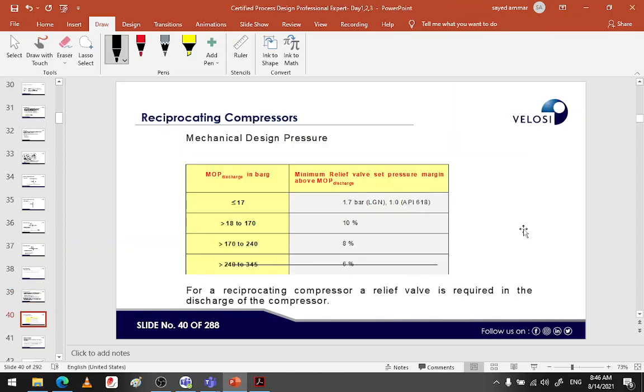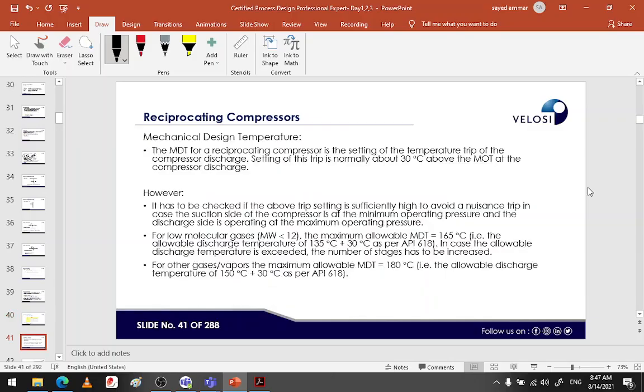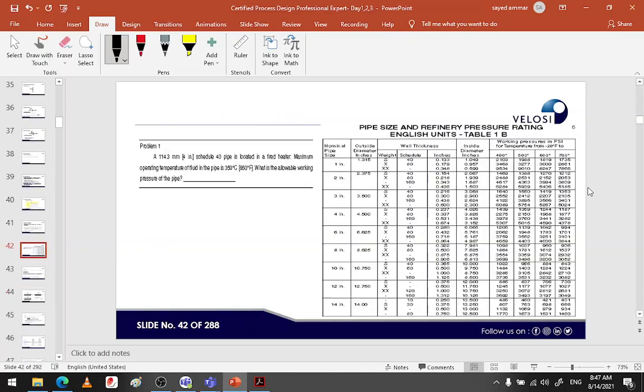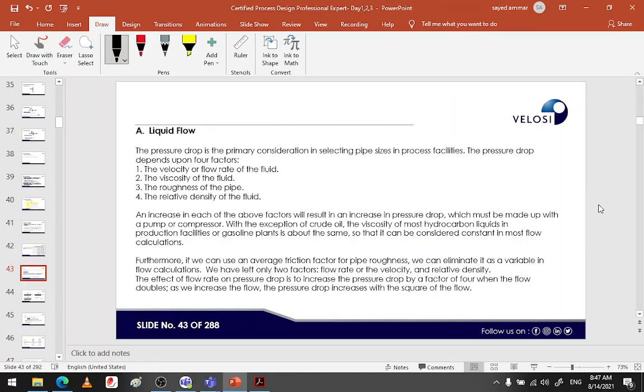This is the same table from another company. Flow less than 17 will add 1.7, between 18 to 170 will go 10% margin, 170 to 240, 8%, from 240 to 345, we are going to add 6%. This is especially for reciprocating compressors and turbines. The same for pipe sizing, liquid flow.